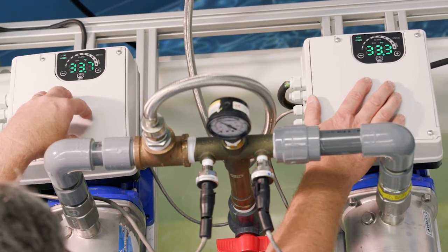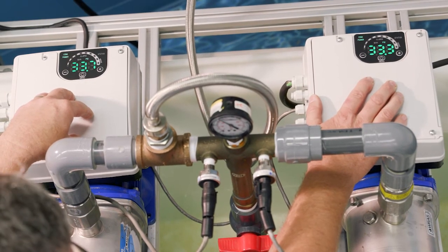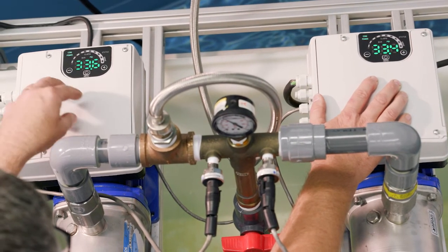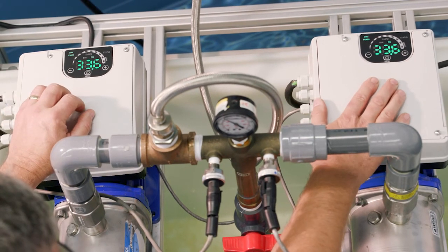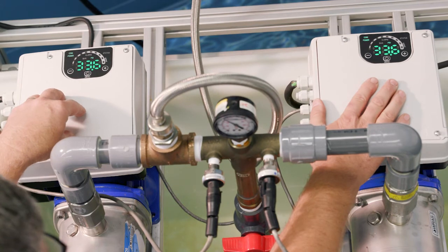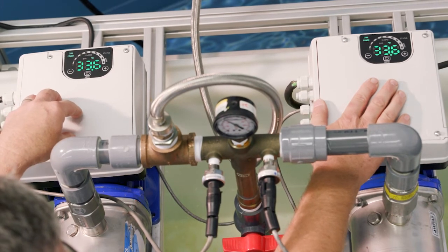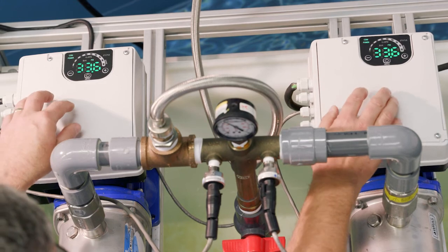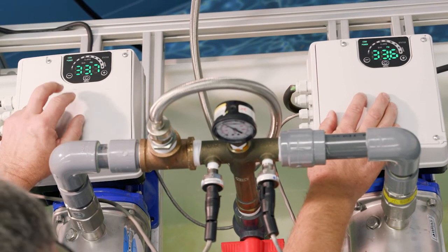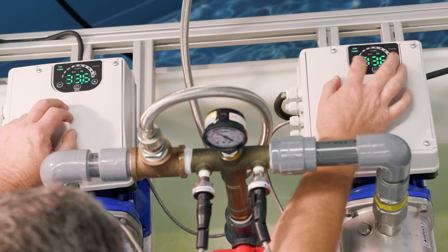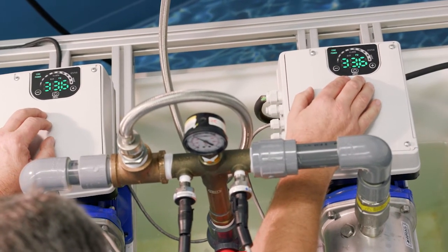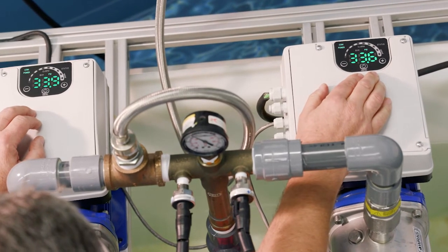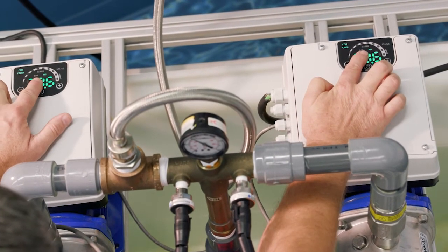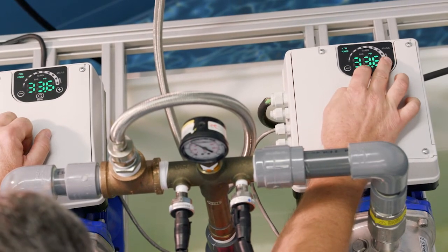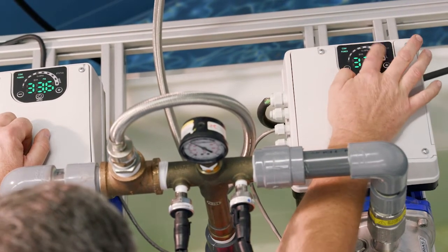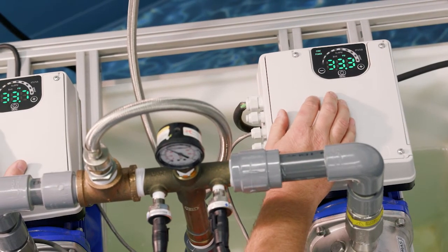Now we can change that alternation. The default is 24 hours, and we did not change that. So when pump 1 can't keep up, it calls on the lag pump to come on. And once that does, then they synchronize, meaning they operate at the same speed. So we're going to try to show you that here. And across the menu bar here the default is PSI. And in order to change that to RPM, I'm going to hit the menu and plus button just so you can see speed across the top bar here on both.